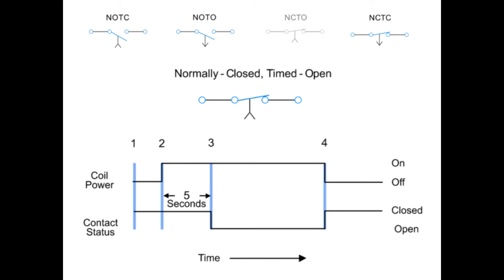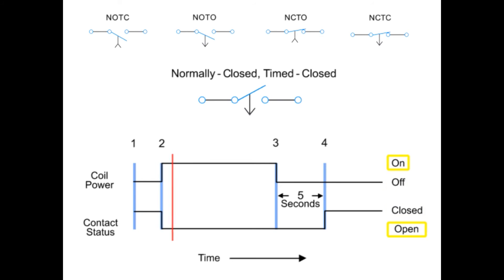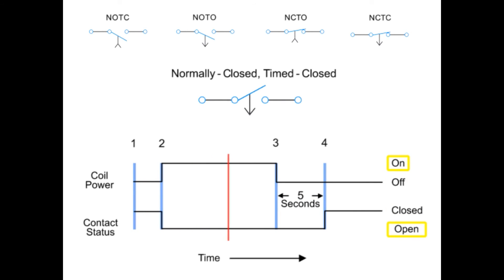The last time-delay relay we will look at employs a normally closed, timed closed contact. Similar to the normally closed, timed open contact, this type of contact is normally closed when the coil is de-energized and opened by the application of power to the relay coil. However, unlike the NCTO contact, the timing action occurs when the coil is de-energized instead of when it is energized. Thus, the contacts open immediately when the coil is energized and close five seconds after the coil is de-energized.